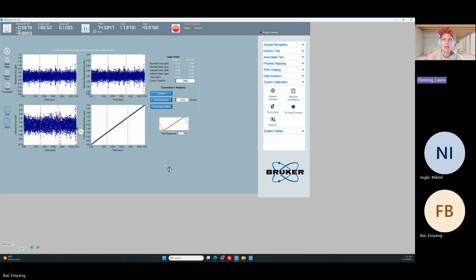So there's some heat there, so sometimes we have to wait a little bit and then run another calibration. But this one actually looks pretty good. Overall, this spread is about 10 micronewtons, which is fine. There's a little noise right here, but without being in the lab, I couldn't tell you precisely why. I'm guessing somebody walked by or a door opened or closed maybe during that calibration.